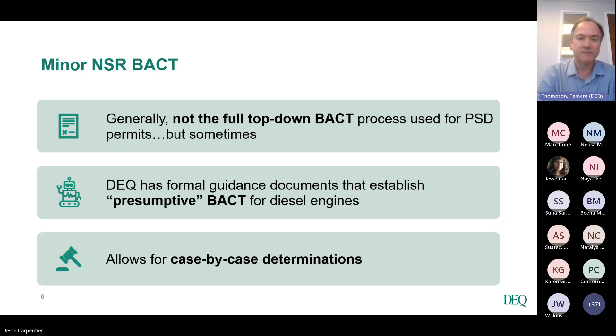Next slide, please. Specifically looking at engines, the presumptive BACT guideline basically distinguishes between emergency and non-emergency engines, and the critical pollutant here is NOx. For emergency engines, we have a standard of 6.0 grams per horsepower-hour, whereas for non-emergency engines, that goes down to 0.6.